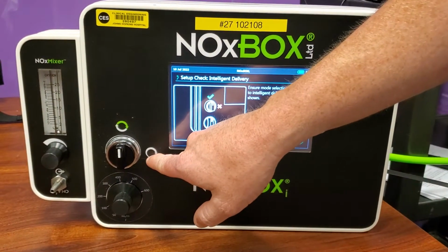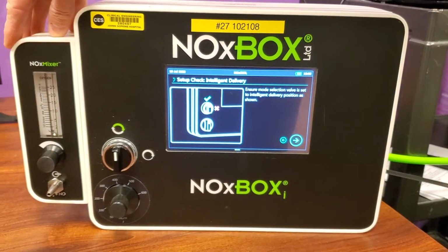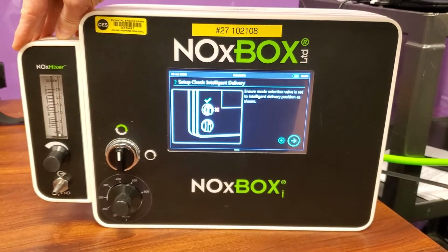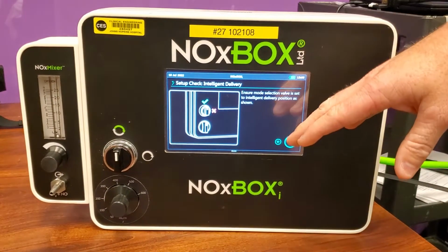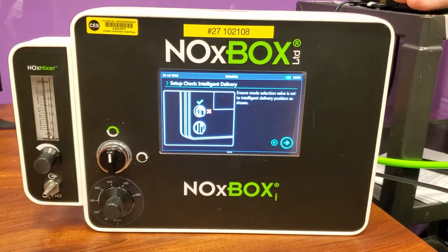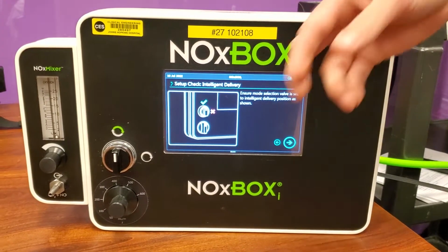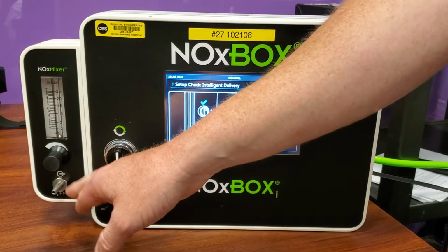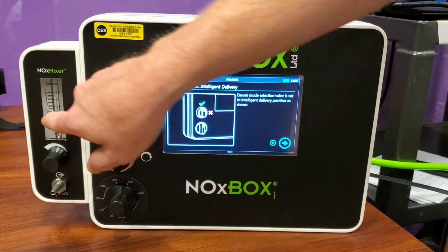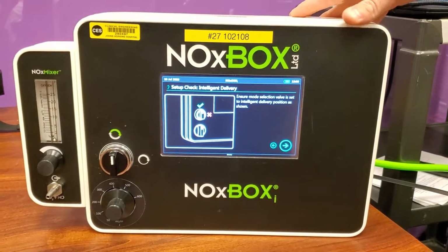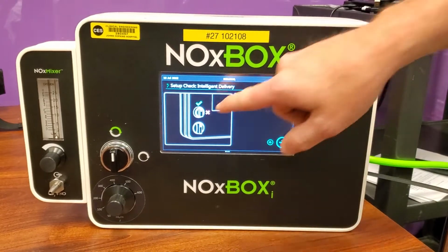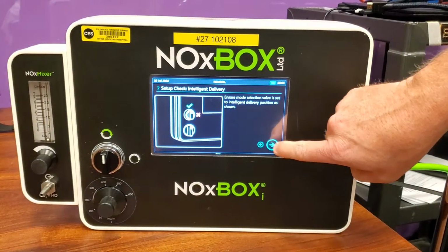If we turn to the side here, that's going to go to our backup NOx Mixer. So for this one, if this gets dropped on the ground and the screen shatters, if for some reason there's a critical failure of some kind and we need to bag the patient, we hook up here and then we would turn this here, and we're going to base everything off of that wheel we were speaking about earlier. So we have confirmed here that we're going to our intelligent delivery.